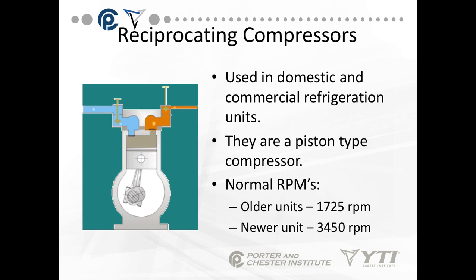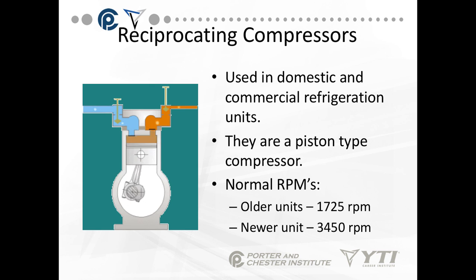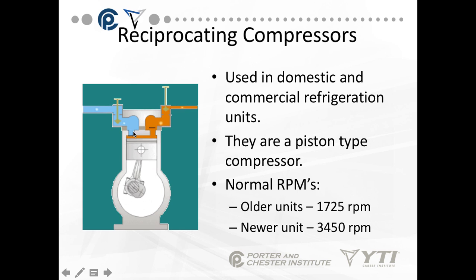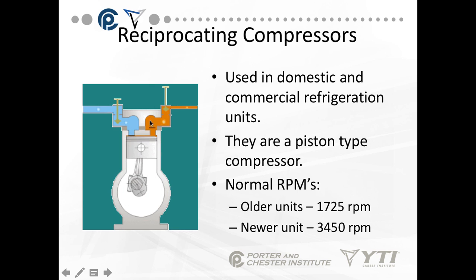The most common type of compressor in refrigeration right now is the reciprocating compressor. It's used in domestic and commercial refrigeration systems. They are piston types — older units operate at 1725 RPM, newer units at 3450 RPM. The piston moves on an off-center rotor with reciprocating action. On the downward stroke, the suction valve opens; on the upward discharge stroke, the discharge valve opens and then re-closes to prevent refrigerant from coming back into the chamber.